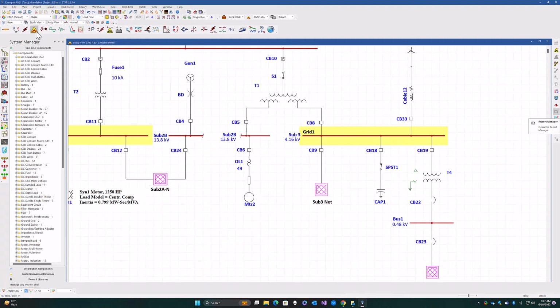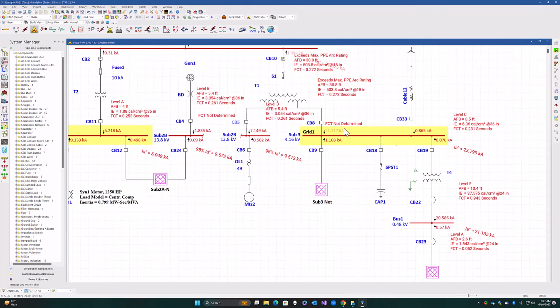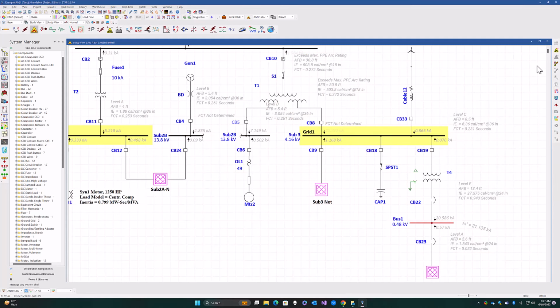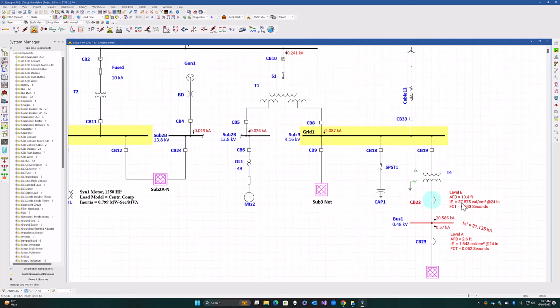So in order to show you the impact of ArcBlok or line side energy isolation, we first switch over to ArcFlash and make sure that we are able to run a simulation here first. We get a warning message that's just letting us know that there's certain things that we need to take care of. And when we look at our simulation results, and just to avoid a lot of detail here, we'll take everything into the don't fault list. We'll go ahead and just fault this particular bus here and run our simulation. So we can see that our energy level for this particular breaker is level E, which is quite high, nearly 40 calories per centimeter square. And in order for us to see the simulation of ArcBlok, let's either switch to a revision, which is ArcBlok, or you can just simply pick up the scenario that we've created in the example file for 1584 ArcBlok.